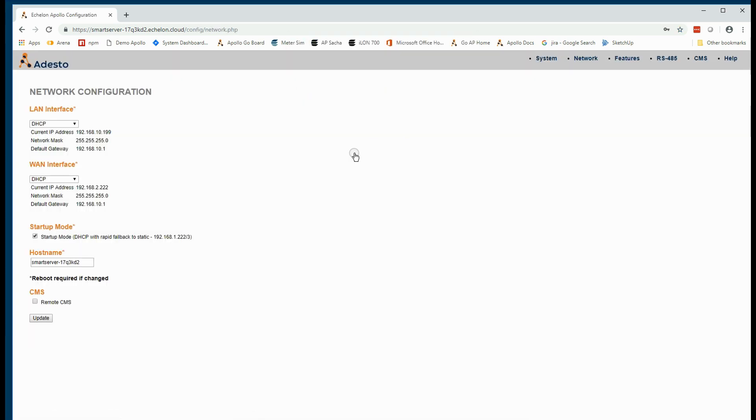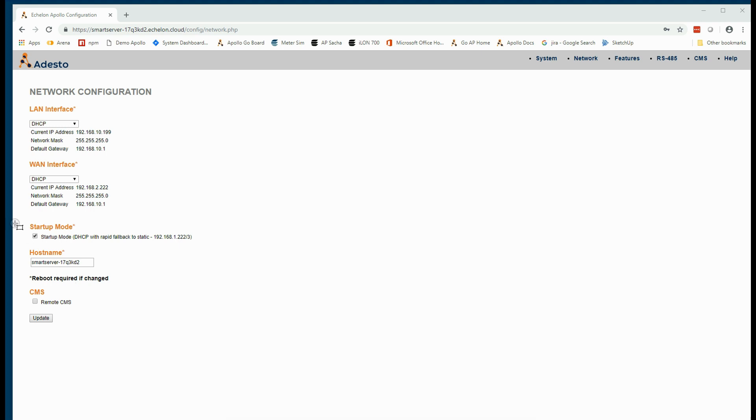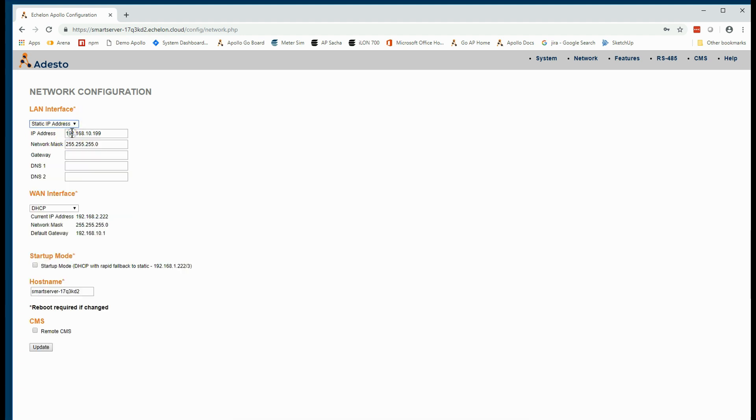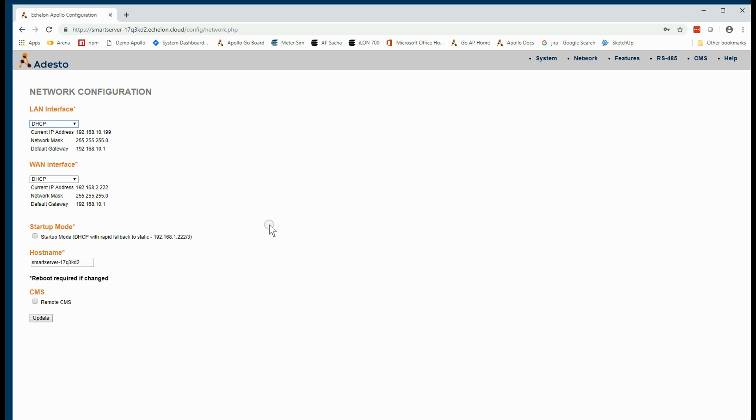When we first log in, we're going to see the overall system configuration. And you'll see here that it's set up to be in startup mode. It's from this network configuration page that we want to establish exactly how we want to operate this Smart Server. Normally, we uncheck startup mode and select between DHCP and static addresses, according to how we want to manage the Smart Server in our internal network.